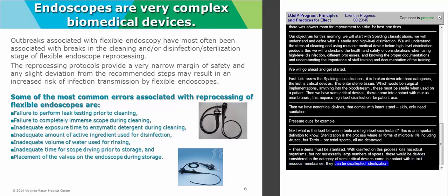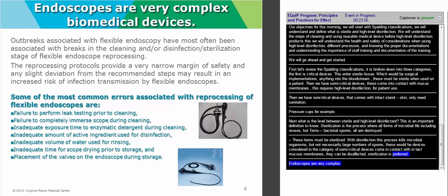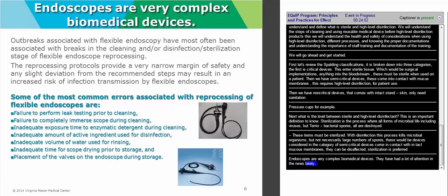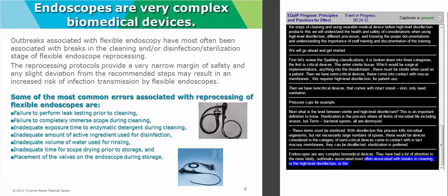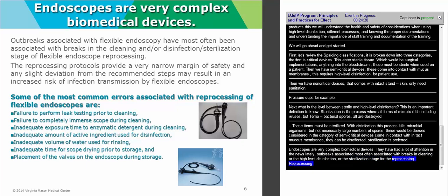Endoscopes are considered semi-critical devices, and they are very complex biomedical devices, and as we all know, they've gotten a lot of hot attention in the news as of late. So outbreaks associated with flexible endoscopy have most often been associated with breaks in either the cleaning or the high-level disinfection or the sterilization stage of flexible endoscope reprocessing. The reprocessing protocols provide a very narrow margin of safety, and any slight deviation from these recommended steps may result in increased risk of infection transmission of flexible endoscopes.